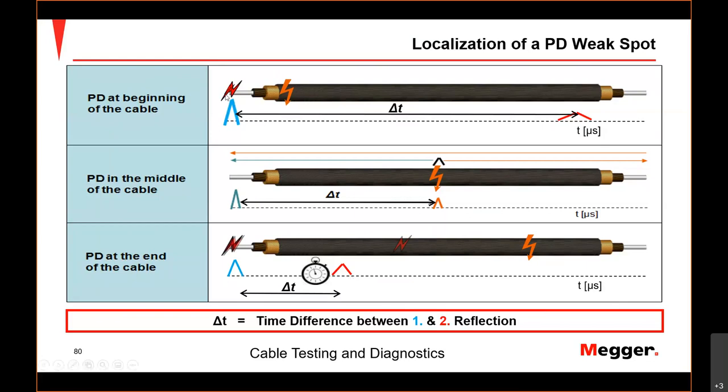When our original pulse is very slim, just like our calibration pulse, then we do not expect any reflection right away close here. We expect a reflection at the far end. And like I said, there's the attenuation curve. And here, if we superimpose our calibration curve, we can see very clearly, does it look like the calibration curve? Then it came from the near end. Does it look different? Then it comes from the far end.